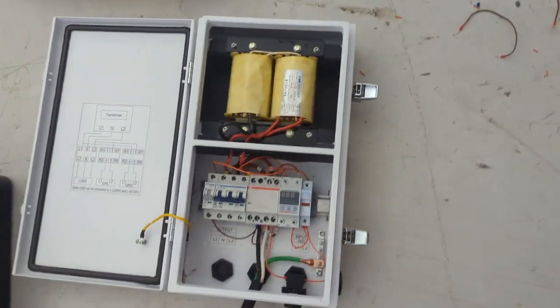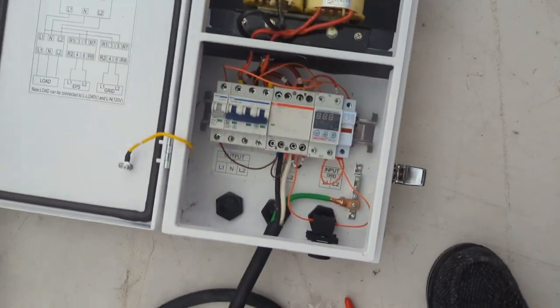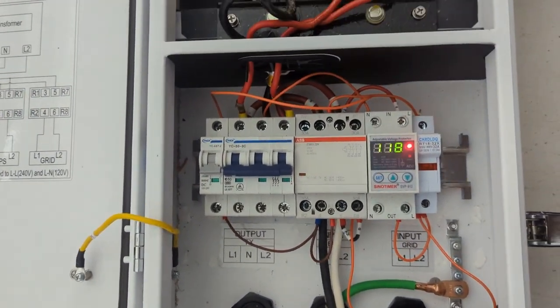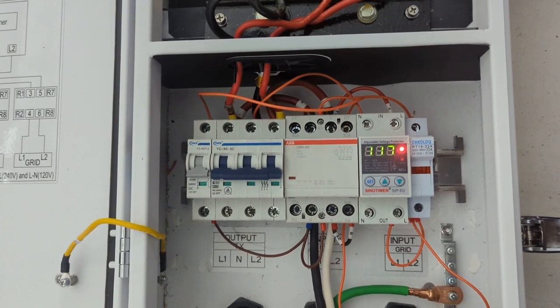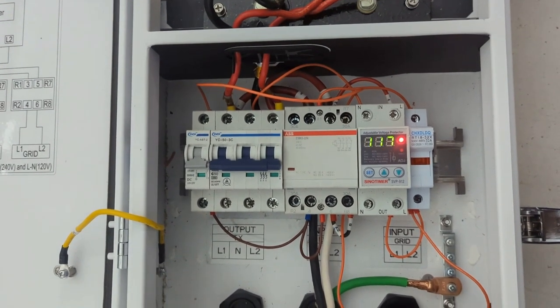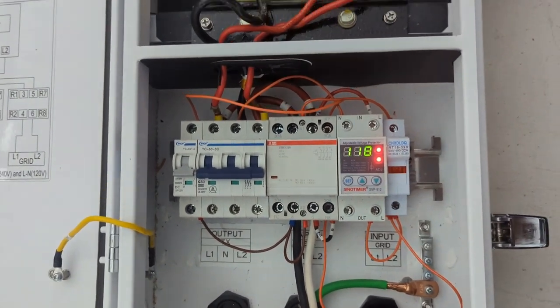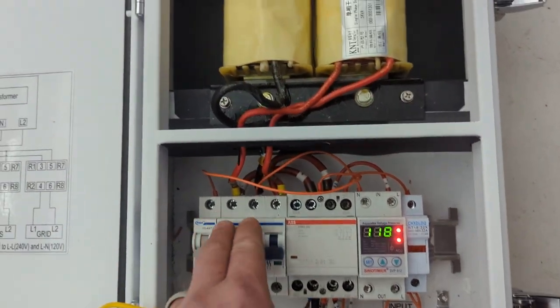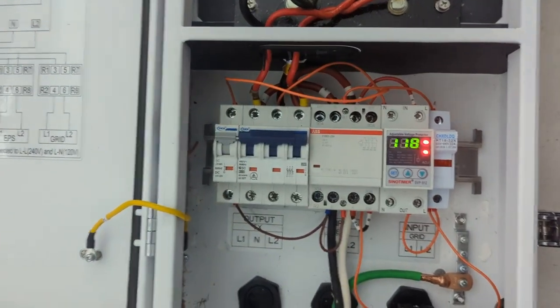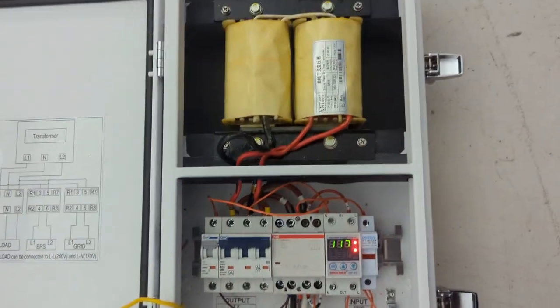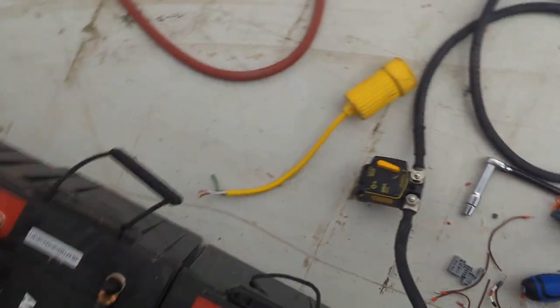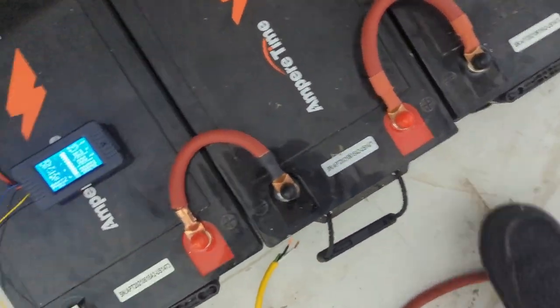So let's go ahead and fire this auto transformer up and see what it does. So now we got the auto transformer rolling here, it's on, it'll stay on. My shunt trip will stay on, so that's all good, that's all working. And we'll come back over here and now we'll check our self-consumption.